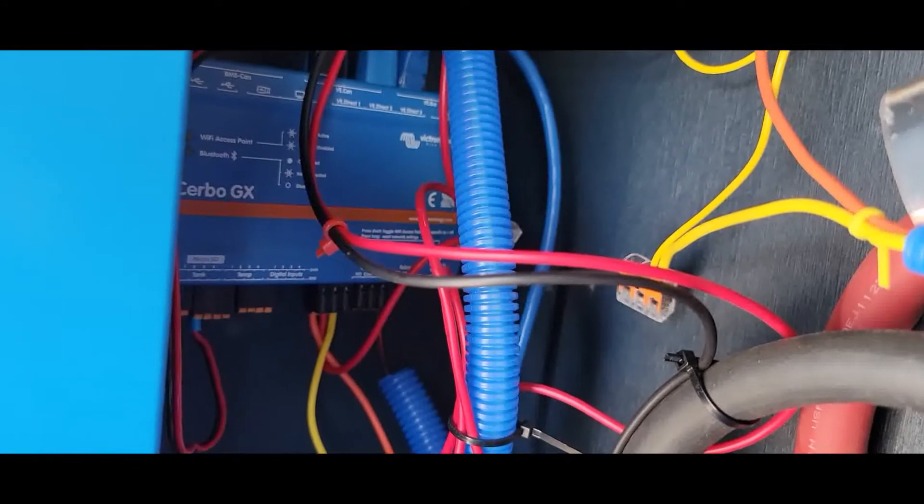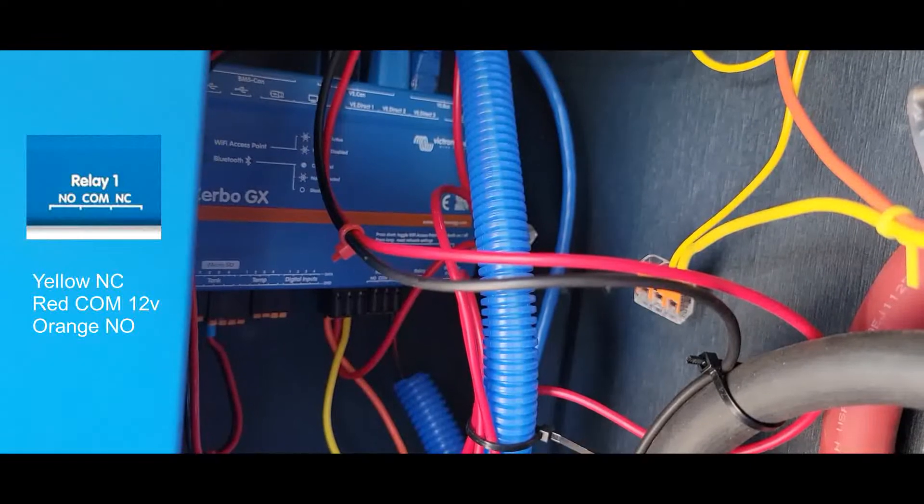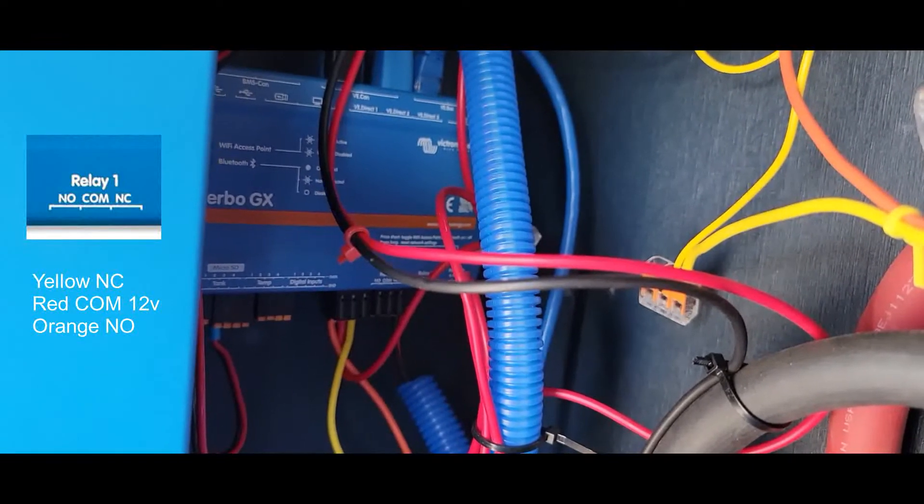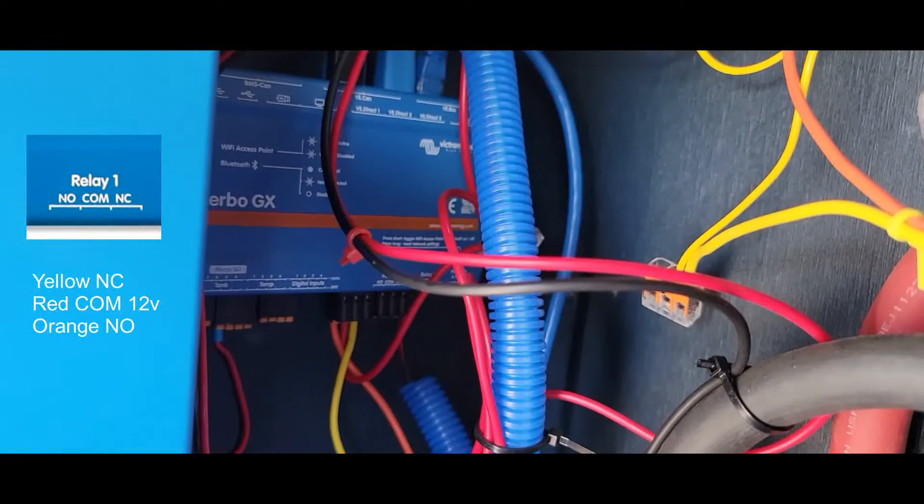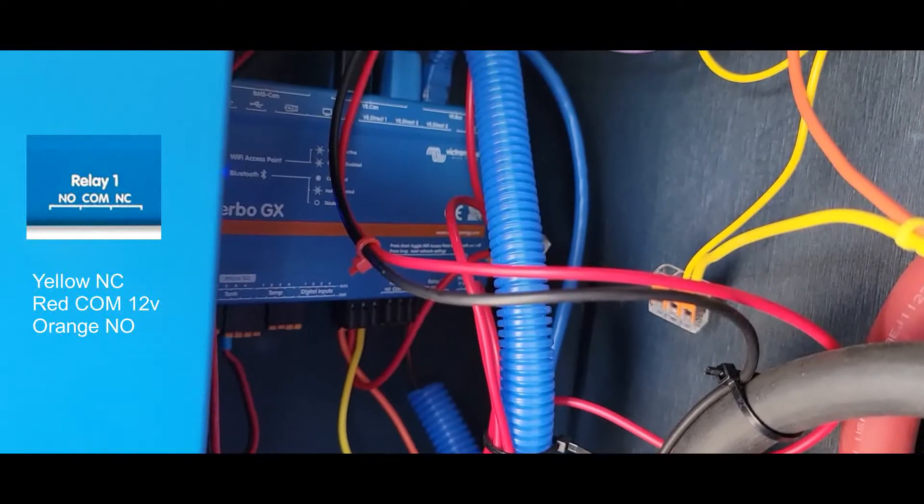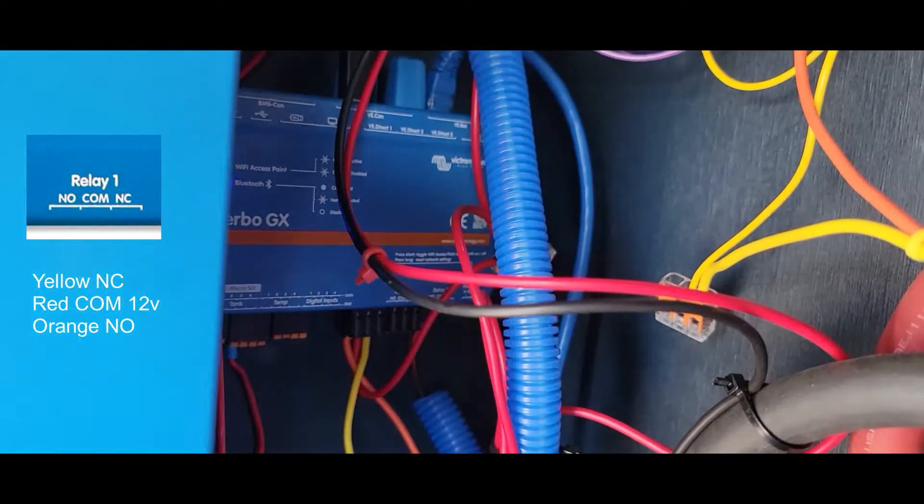Looking at the Cerbo GX, you can see that there's a positive wire going into the common, which is the middle one. And then the stop is on the right-hand side, which I believe that's the normally open. And then the start is on the normally closed.